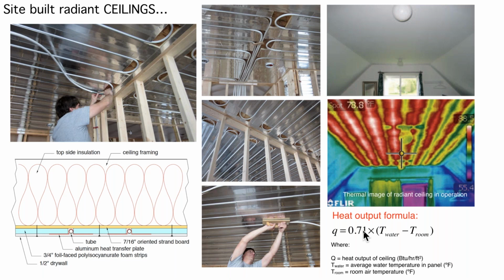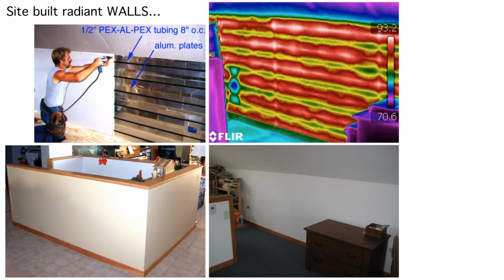And of course, we could go even lower if our heat load in the space allows us to. So this is definitely a heat emitter system that could be well suited to work with the air-to-water heat pump, as well as a geothermal water-to-water. Now, if you take that same system and just turn it on its side, you get a radiant wall. It's literally the identical construction. It's just on a vertical plane versus the ceiling plane.